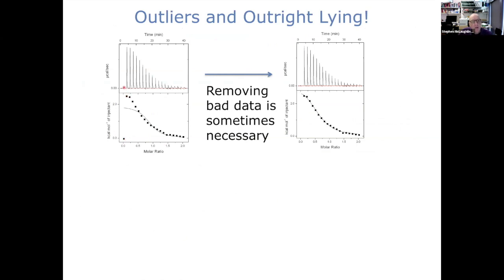We need to do that because when you have the titrant in the syringe and you put it into the cell, sometimes you might get a bit of diffusion from the cell into the syringe, and vice versa. So we always titrate a very, very small volume just to get rid of that sample, and then we have to remove it in the data to be able to fit.